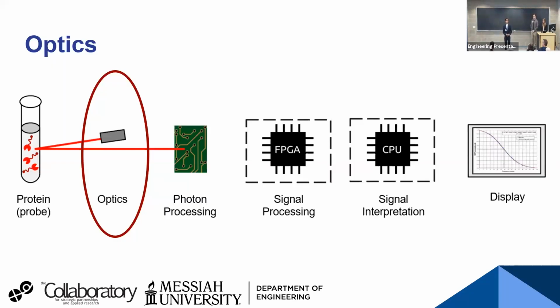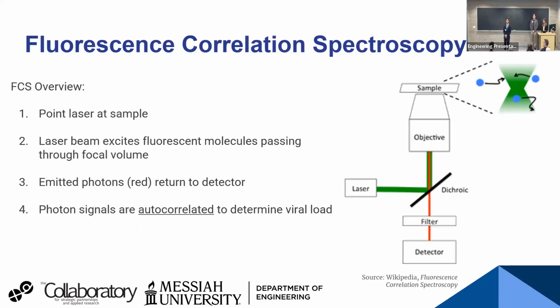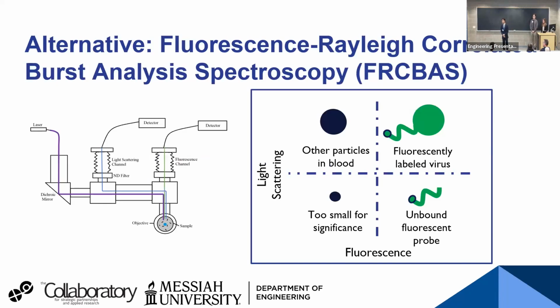So to detect HIV in a viral blood sample, we use a fluorescent probe that binds to the protein that's on the surface of an HIV particle. Our optic system is able to then detect this fluorescent probe. To do this, our optic system uses a method called fluorescence correlation spectroscopy. First, we shine an excitation laser at the fluorescent probe, and the fluorescent probes, when they're excited, will emit an emission wavelength that is picked up by our detector. Then those photon signals are autocorrelated to determine a viral load diagnosis.